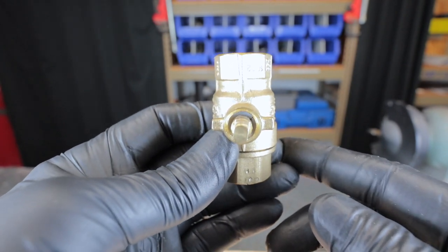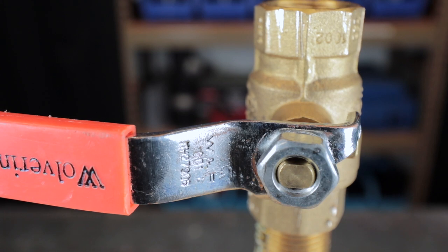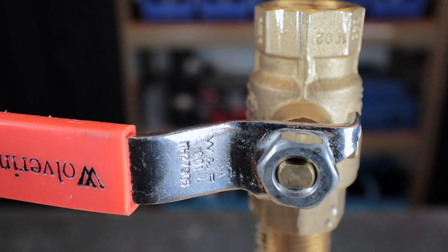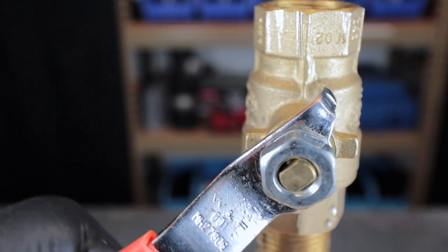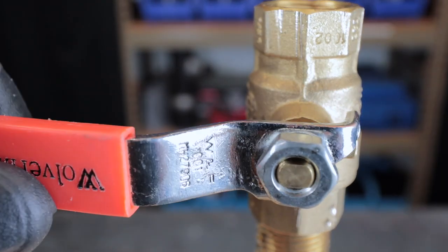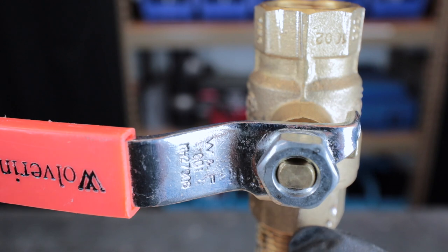Generally a shutoff valve is basically sitting there for service and sometimes it sits there for years and years. The first person who comes along and touches it, whether it be a ball valve or gate valve, you go to shut it off because you have to service something. As soon as you start turning the thing, you're going to see water start dripping out from the packing gland and then people start to freak out. There's nothing to get nervous about.